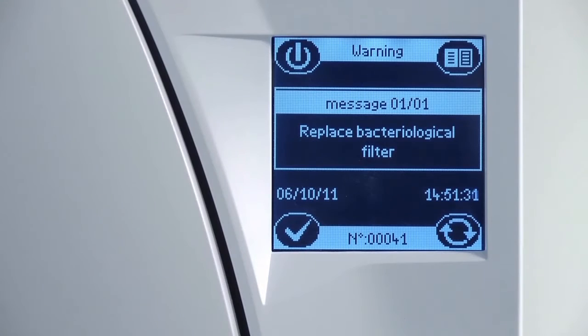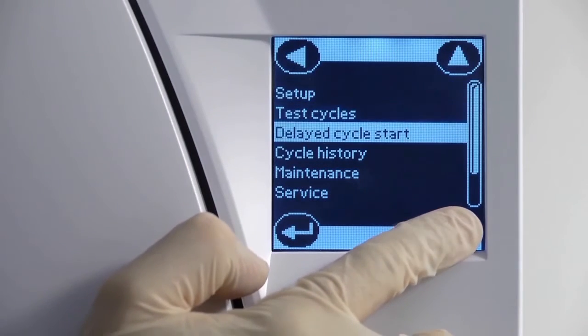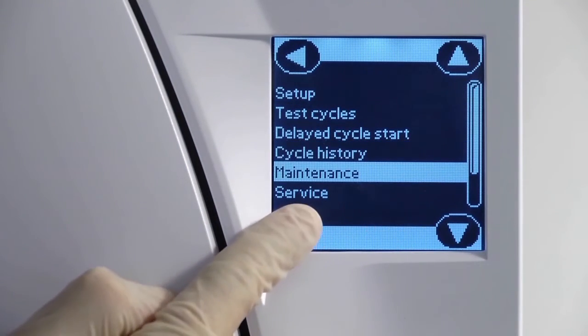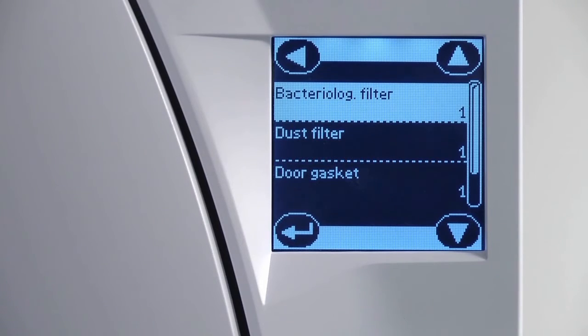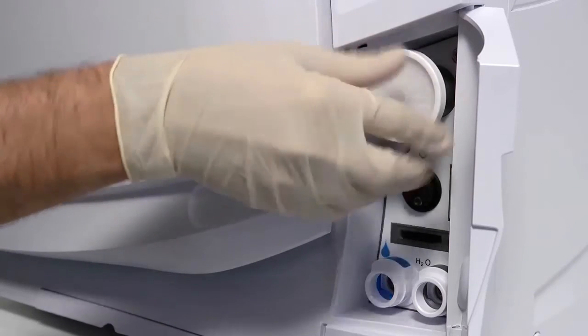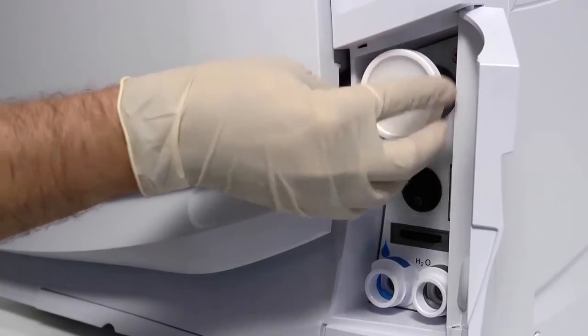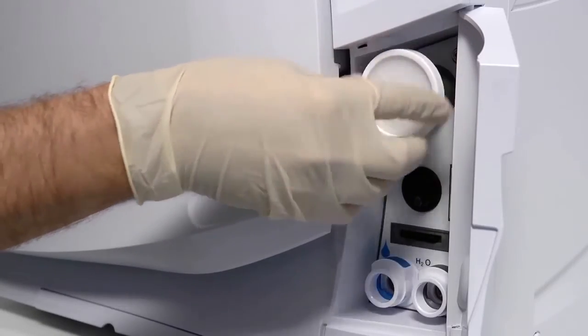Your Lisa sterilizer will automatically prompt you when the life of the bacteriological filter has expired and needs to be replaced. Alternatively, you may view the number of cycles completed by the filter from within the maintenance screen of the menu. To change your filter, unscrew the filter in a counterclockwise direction until it can be fully removed.